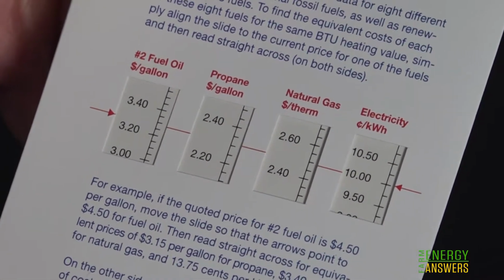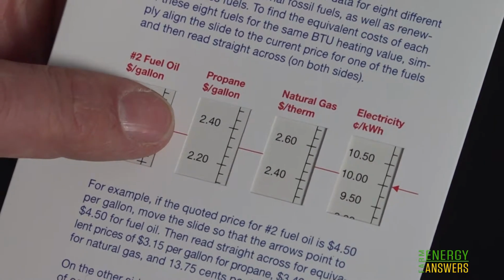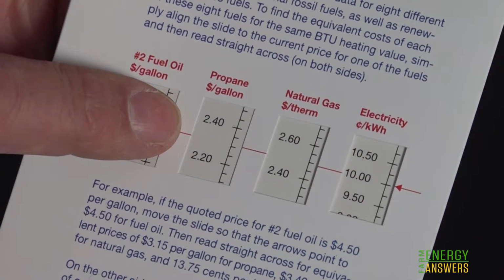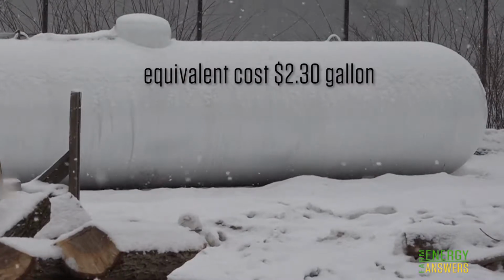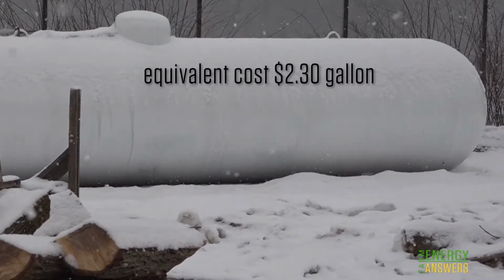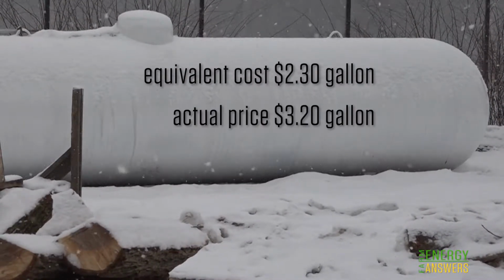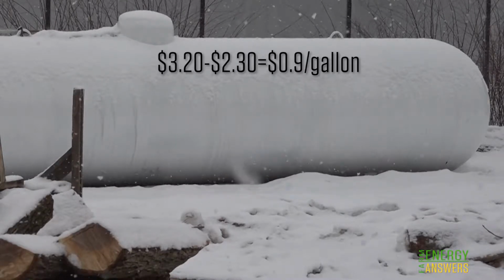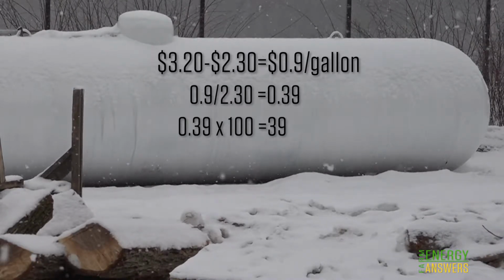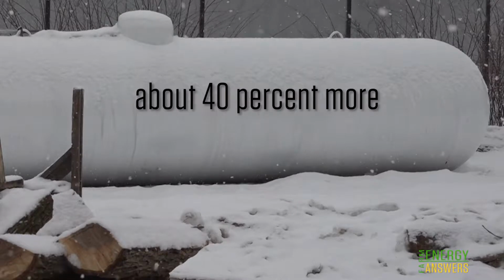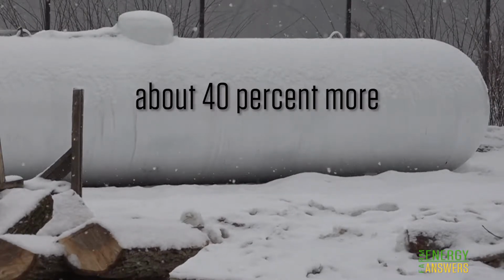The Energy Selector now shows that the equivalent cost for propane is about $2.30 per gallon. Thus, if propane were available for less than $2.30 per gallon, it would be cheaper to use than electricity. But the actual price of propane for the greenhouse grower is $3.20 per gallon. That's much more. In fact, propane would be about 40% more expensive to use than electricity in this example.